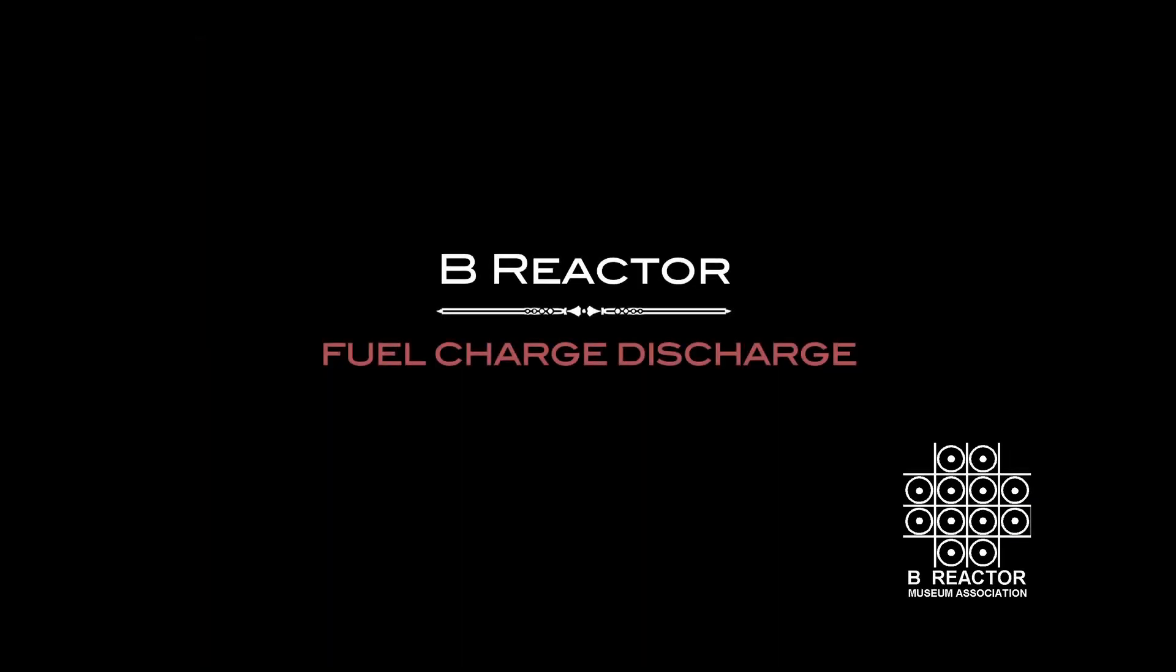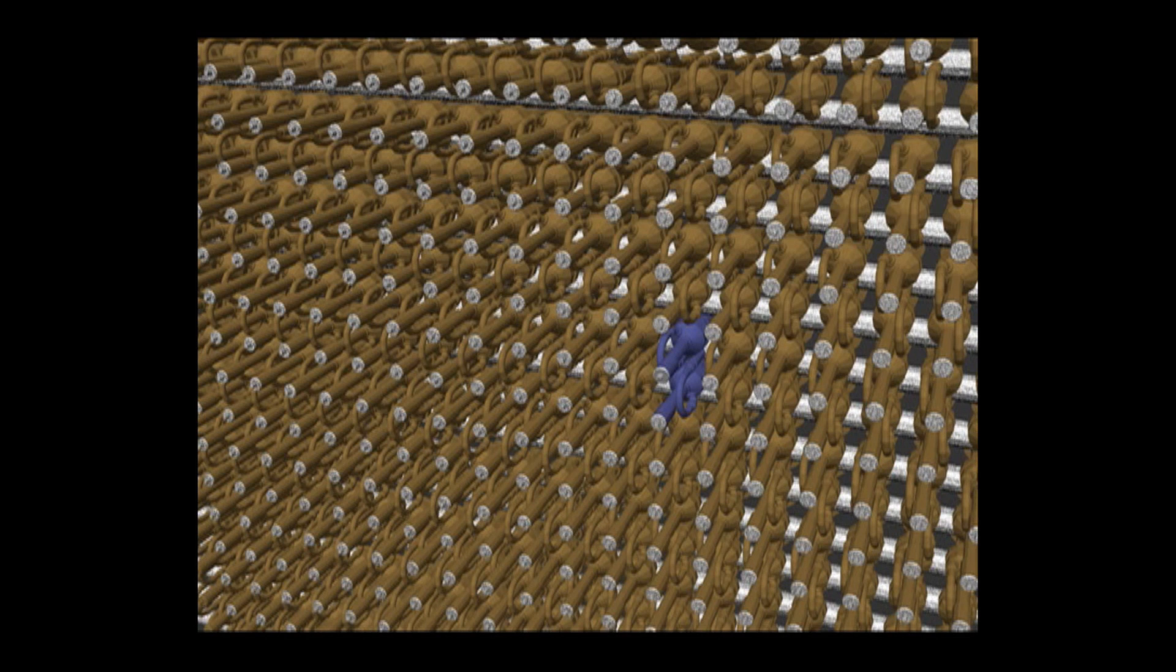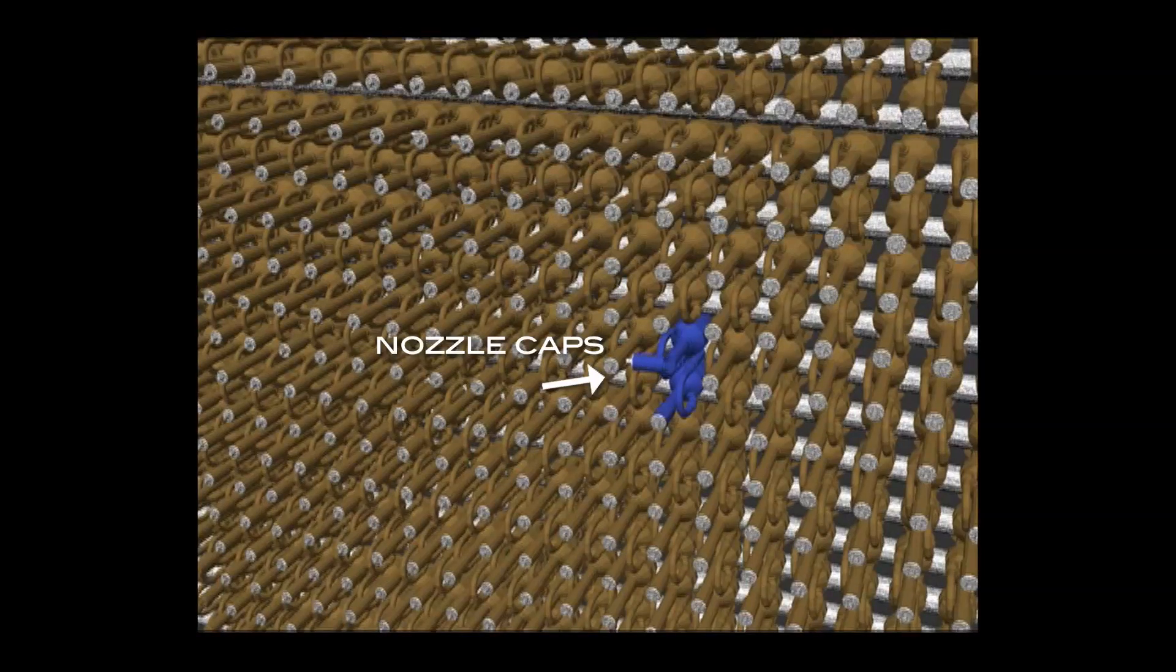Fuel Charge Discharge. To load a fuel column the reactor is shut down, the water in the tube row of the tubes to be charged is reduced to a trickle flow, and nozzle caps on both ends of the tubes are removed.